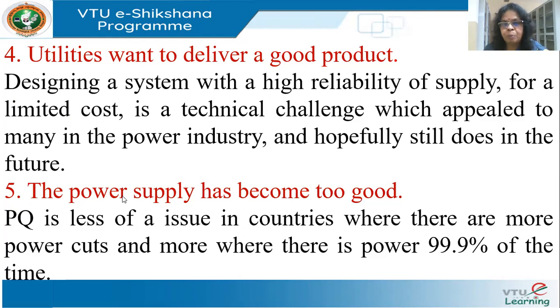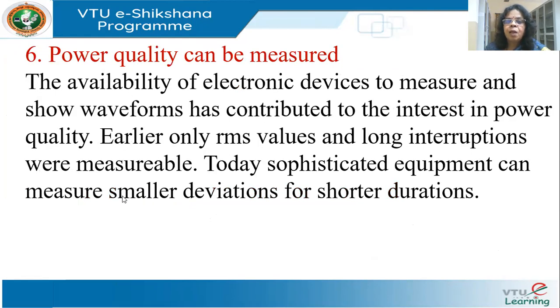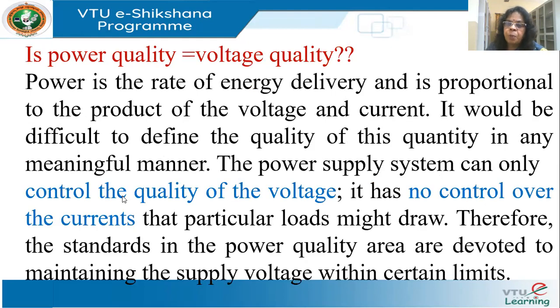So now we talk of quality - once our basic requirement is satisfied, you want better quality. And today we can measure power quality - you talk of harmonics, yes, I have meters which can measure it, measure this frequency spectrum. You talk of a sag, a small disturbance for a few cycles, that can be measured. Earlier we didn't have such sensitive measuring equipment - we could only measure long time RMS disturbances, instantaneous measurements were not possible. But with digital electronics it's possible, and so we have very good quantification of the power quality disturbance. These are some of the reasons why the focus has shifted to power quality.